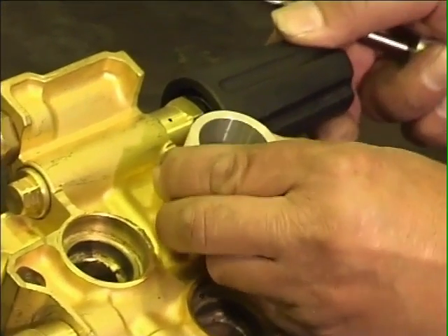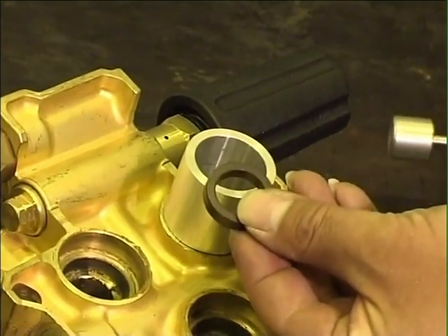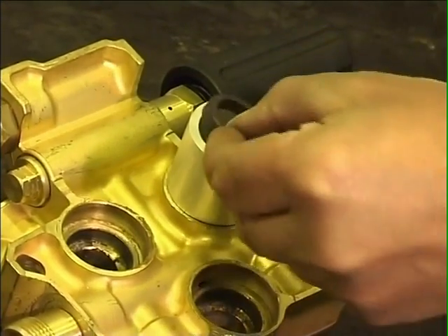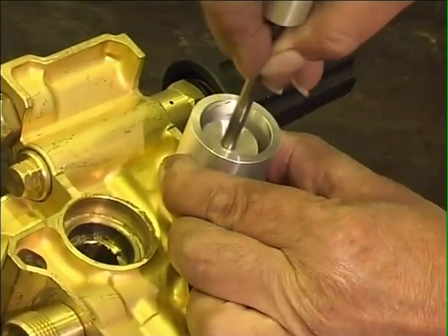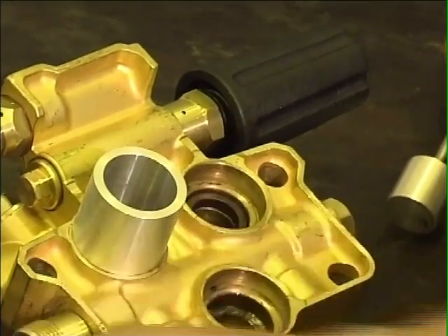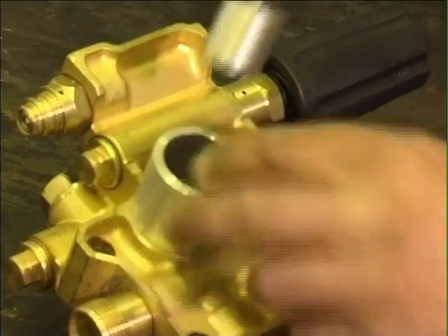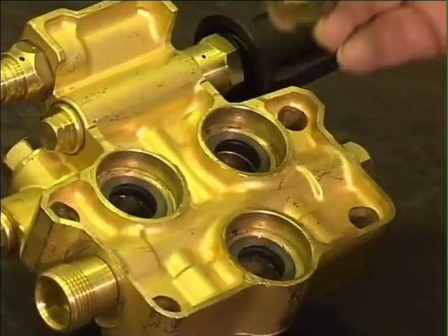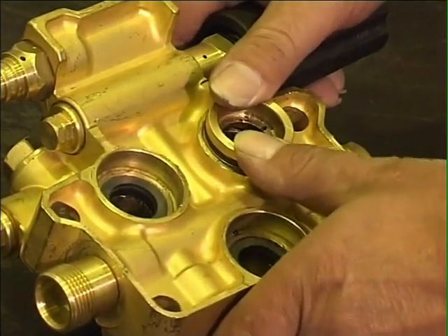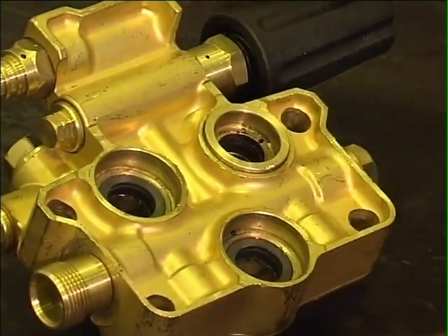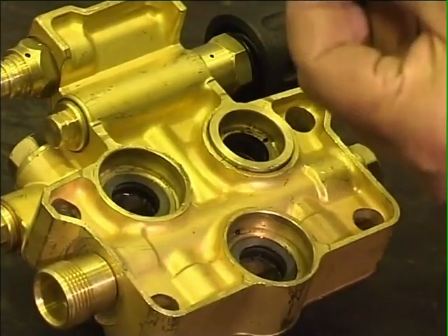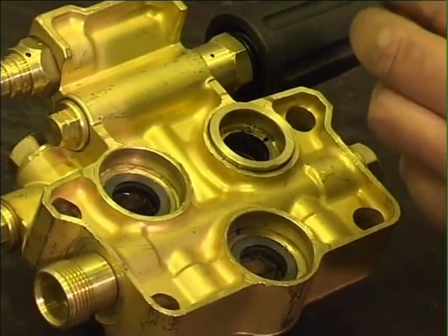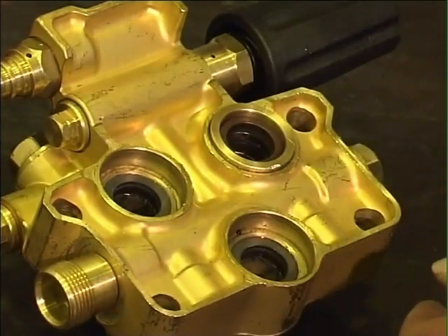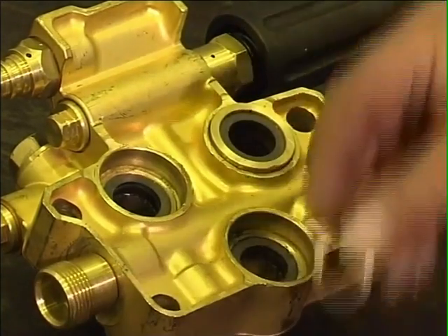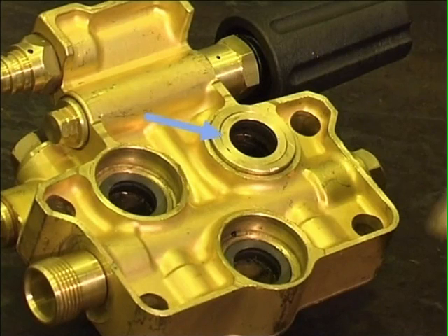To facilitate assembling of spare parts, we offer special tools. You can obtain these from us. When replacing sealing sets, you must respect the order and the installation direction. First, the hard ones without pressure ring. Then the leakage ring, and the soft seals with pressure ring. Take a look in your operating instructions to determine whether you must use a brass intermediate ring for this type of pump.